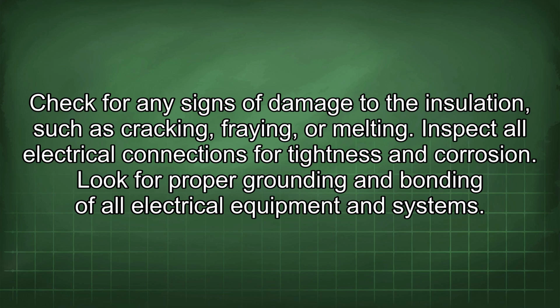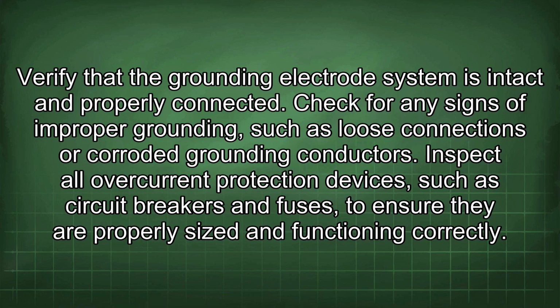Look for proper grounding and bonding of all electrical equipment and systems. Verify that the grounding electrode system is intact and properly connected. Check for any signs of improper grounding, such as loose connections or corroded grounding conductors.